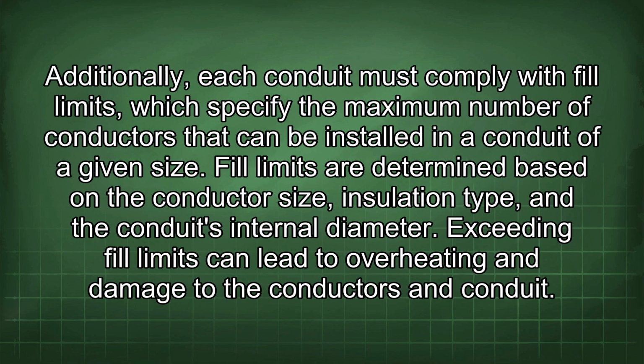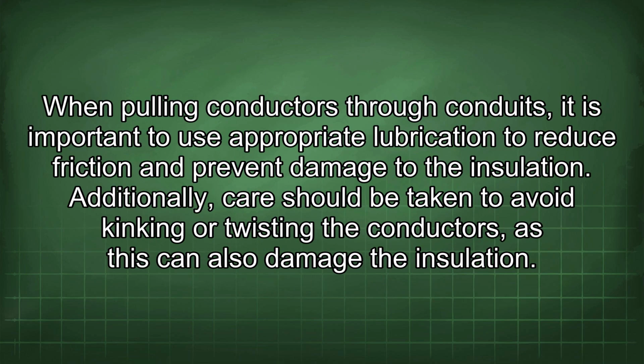Additionally, each conduit must comply with fill limits, which specify the maximum number of conductors that can be installed in a conduit of a given size. Fill limits are determined based on the conductor size, insulation type, and the conduit's internal diameter. Exceeding fill limits can lead to overheating and damage to the conductors and conduit. When pulling conductors through conduits, it is important to use appropriate lubrication to reduce friction and prevent damage to the insulation. Additionally, care should be taken to avoid kinking or twisting the conductors, as this can also damage the insulation.